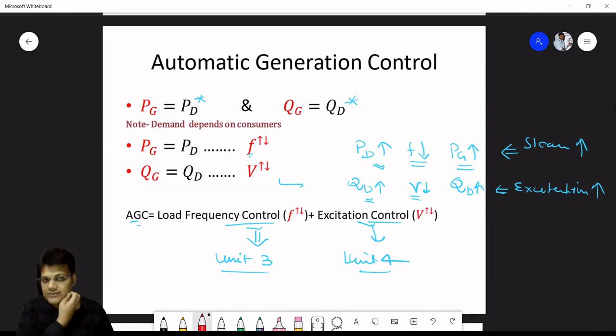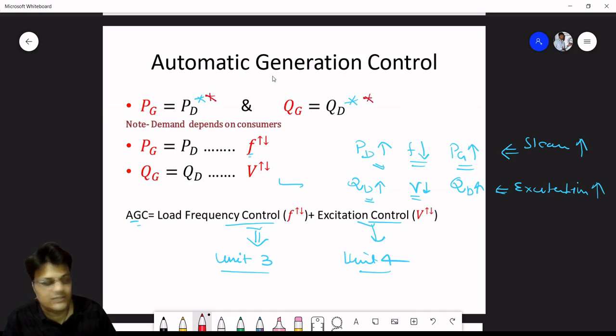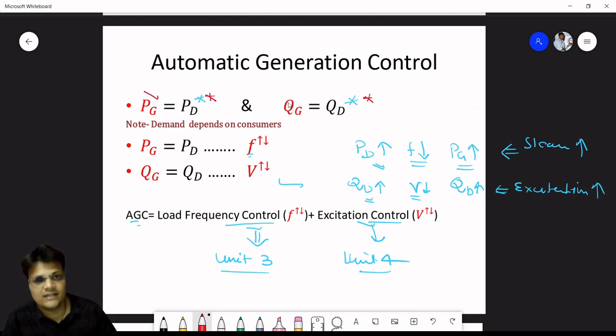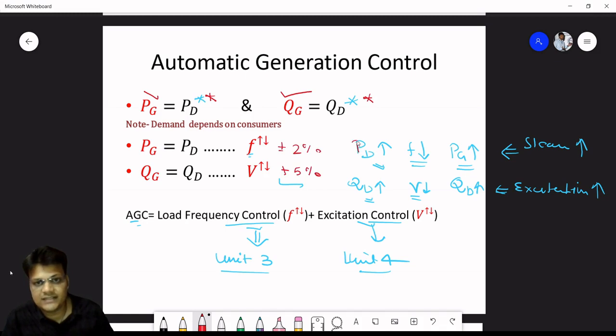Automatic generation control: the demand — both active and reactive — is continuously varying. We cannot tell the customer to increase or decrease demand. So we must match active power generation and reactive power generation to demand, maintaining frequency within ±2% and voltage within ±5%.